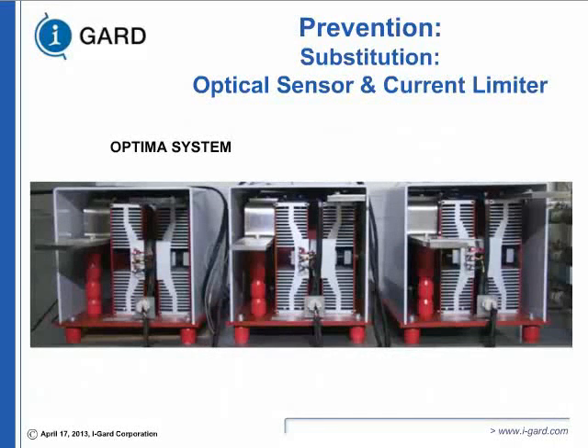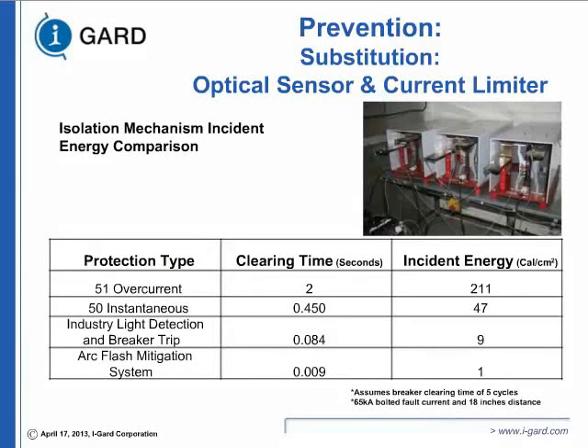This is a new concept being introduced. Right now, it does not matter how fast you can detect or isolate it; the breaker takes 3 to 5 cycles to trip, because a breaker is an electromechanical device. If you could have a solid-state device, which is the Optima system, that doesn't need that kind of delay, it can trip in about 9 milliseconds total: 1 millisecond detection time and 8 milliseconds for operation. It is available, as I understand, in the industry at about 2000 amp and 50K at 480 volt.